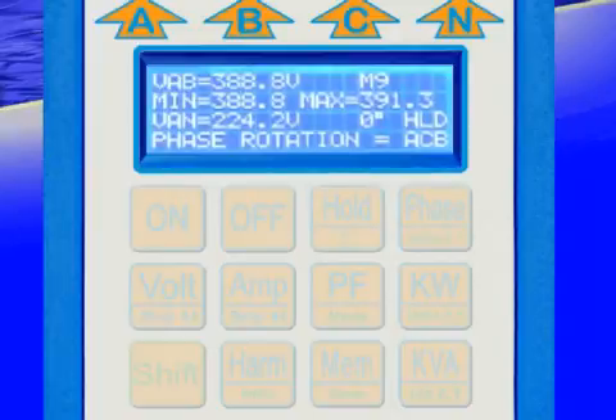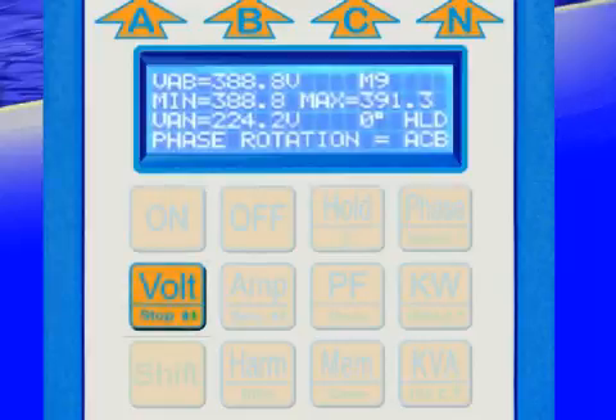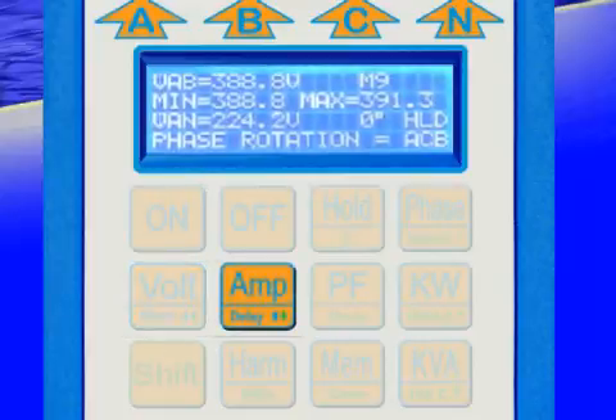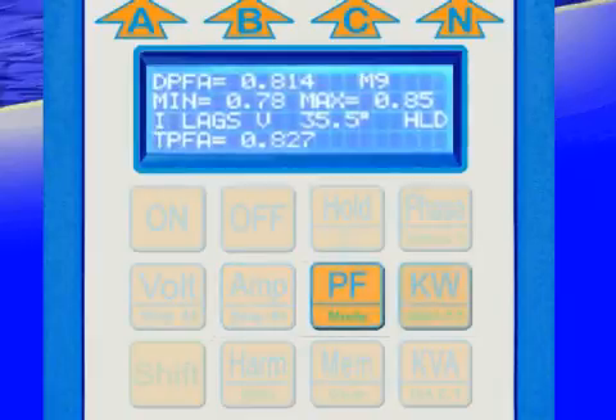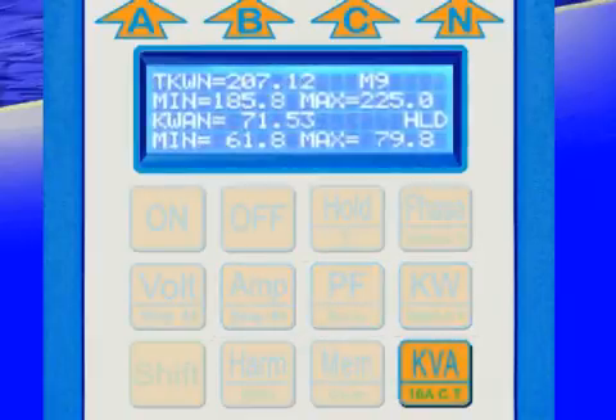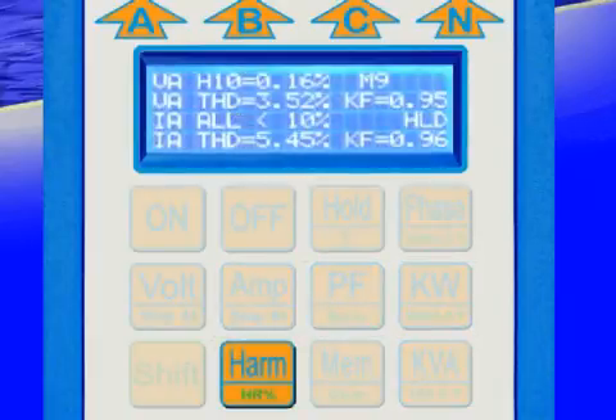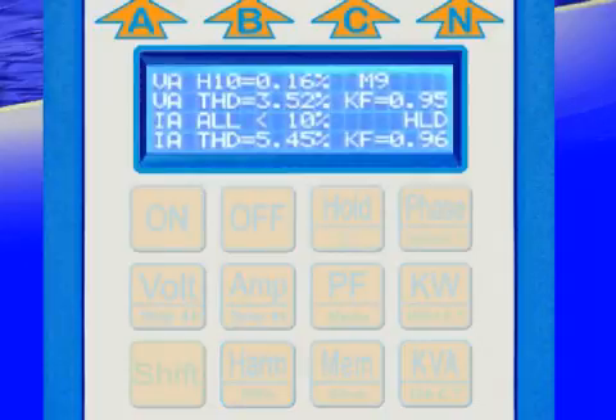Now, for demonstration purposes, I will show you previously recorded data and show you the different functions Harmonitor can perform. First, phase voltages, phase currents, power factor, kilowatt, kVA, and harmonics. The harmonic display shows individual harmonics for both current and voltage, as well as the total harmonic distortion for the phase.